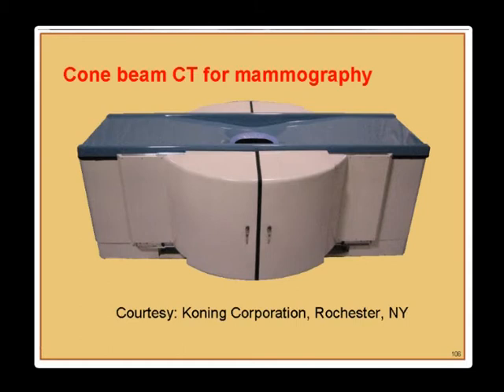A 10-second breast scan can reveal lesions otherwise obscured by anatomical noise, since this is a true CT. Compared to standard CT, flat-panel CT introduces some scatter because a conventional focused grid cannot be used with a cone beam geometry, but scatter is addressed through pre-processing and post-processing.